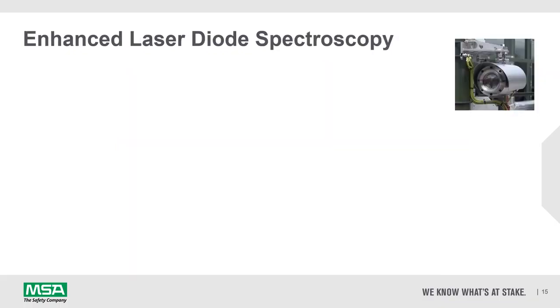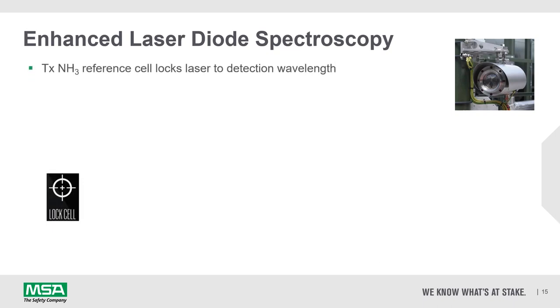Open path laser-based gas detection uses a technique called enhanced laser diode spectroscopy. The transmitter with its laser uses an ammonia filled reference cell as part of a control feedback loop to ensure that the laser remains locked on the detection wavelength. The reference cell is sealed for the life of the product and doesn't require any refilling or replacement.